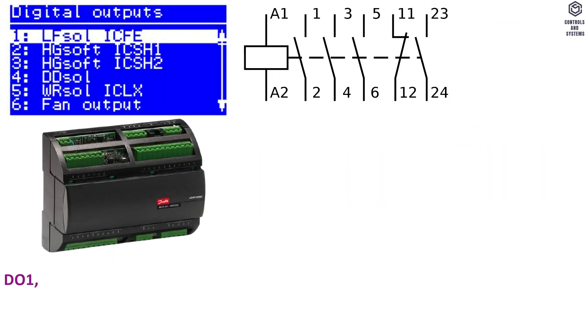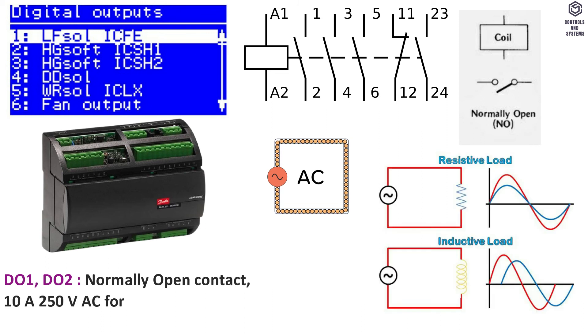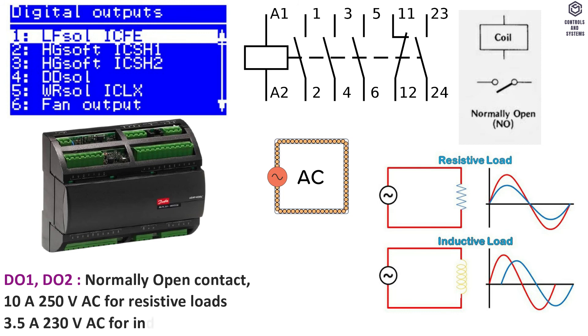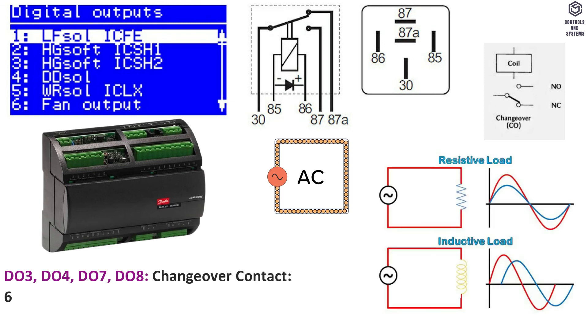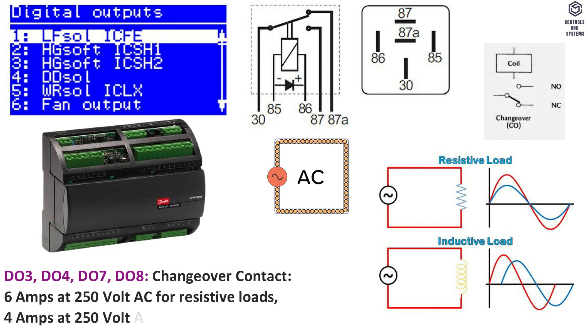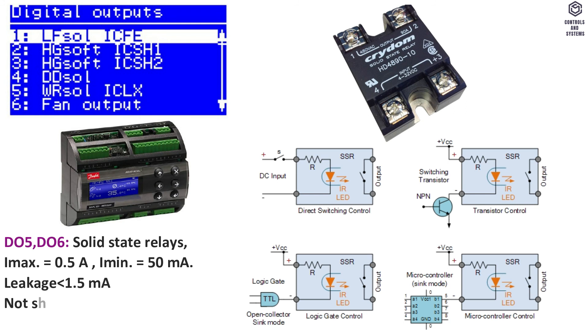Digital outputs — normally open contact: 10A at 250V AC for resistive loads, 3.5A at 230V AC for inductive loads. Change-over contact: 6A at 250V AC for resistive loads, 4A at 250V AC for inductive loads. Solid state relays: I maximum 0.5A, I minimum 50mA, leakage less than 1.5mA, not short-circuit protected.